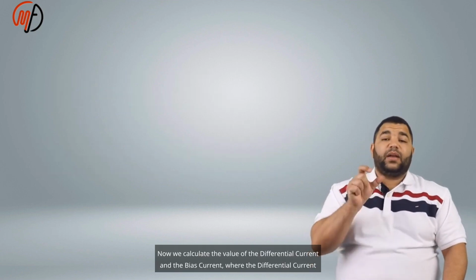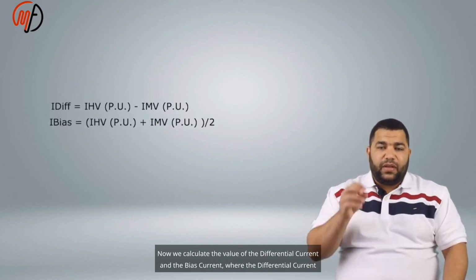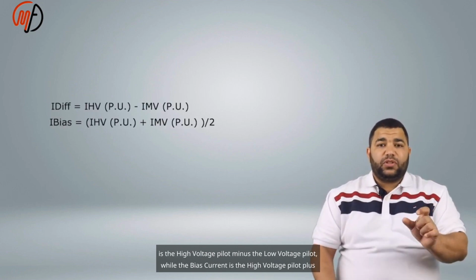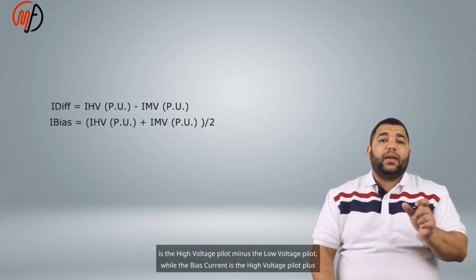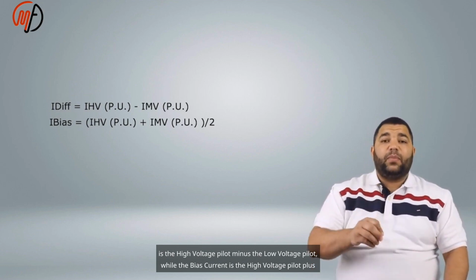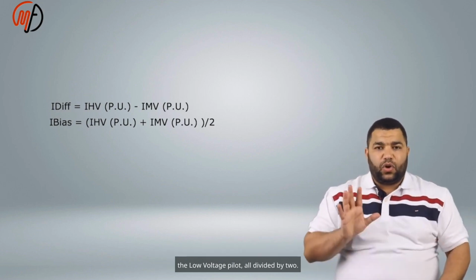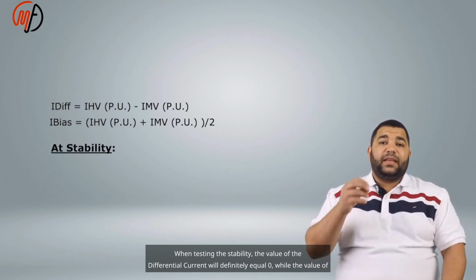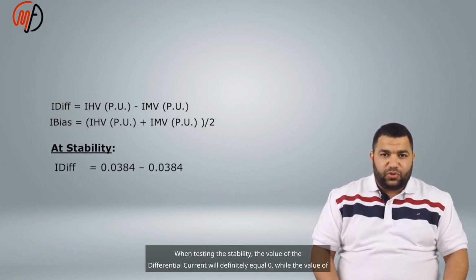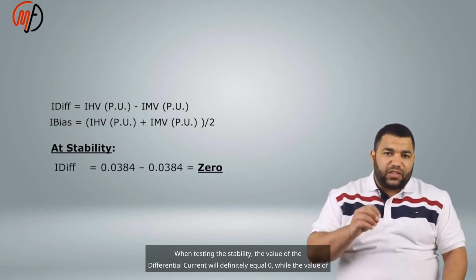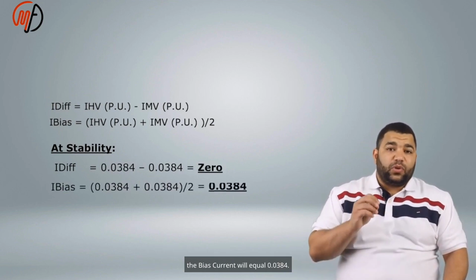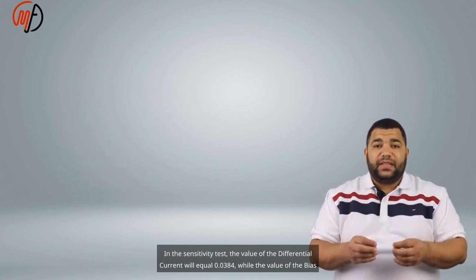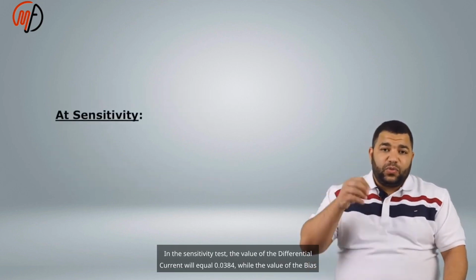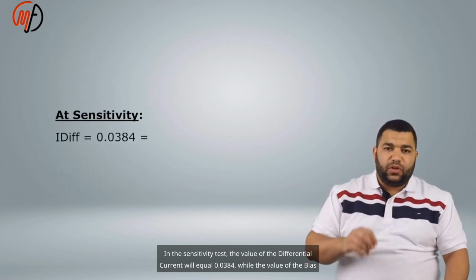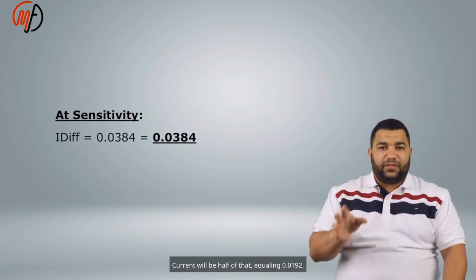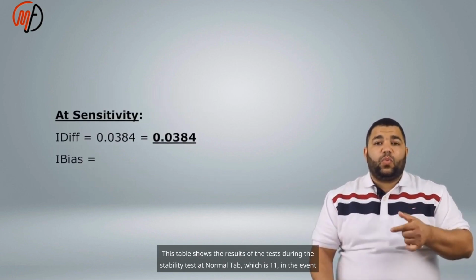Now we calculate the value of the differential current and the bias current, where the differential current is the high voltage pilot minus the low voltage pilot, while the bias current is the high voltage pilot plus the low voltage pilot, all divided by 2. When testing the stability, the value of the differential current will definitely equal 0, while the value of the bias current will equal 0.0384. In the sensitivity test, the value of the differential current will equal 0.0384, while the value of the bias current will be half of that, equaling 0.0192.